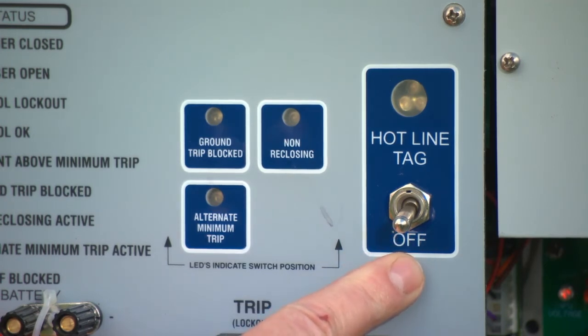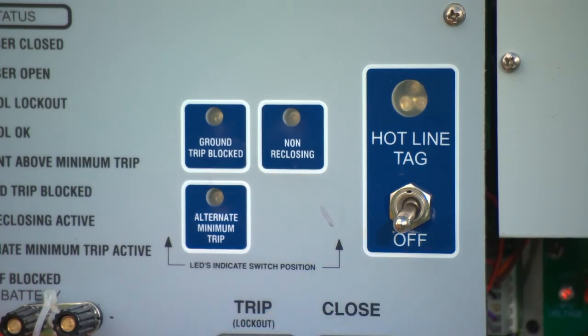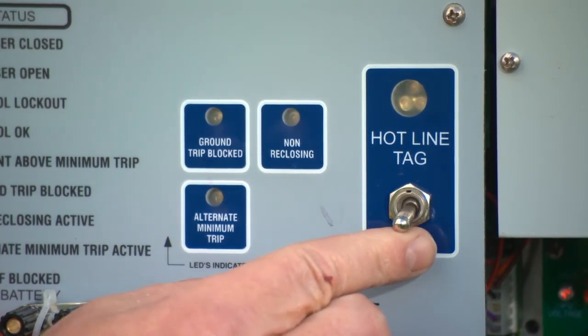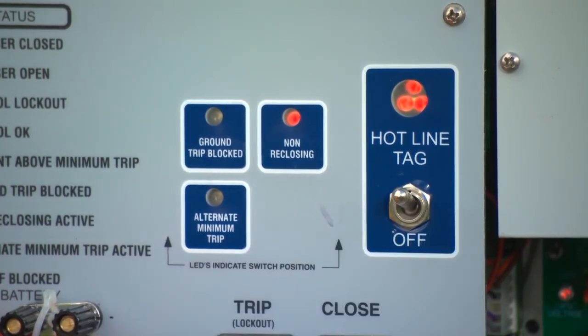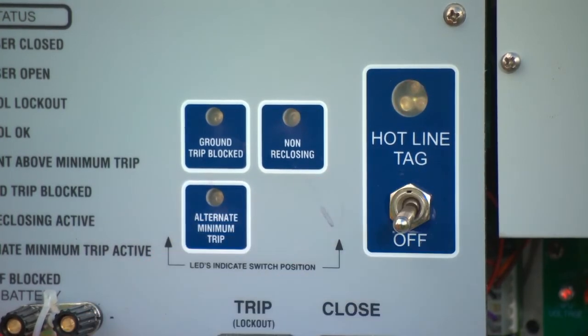If the hotline tag switch is applied, the unit goes into a non-reclosing state and also does not allow any supervisory or remote communications to change the state. In-field personnel must physically apply and remove the hotline tag.